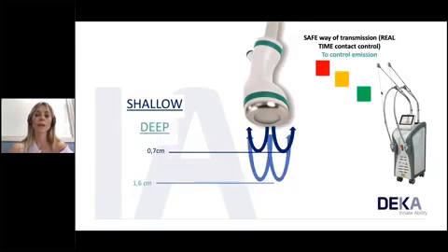And the deep end piece instead will reach 1.6 centimeter, and then it will recall back from the electrode. So the transmission is safe because no vital organs will be involved. It's safe for the patient, but it's also safe for the physician, because even if we carelessly lose contact with the skin, we are sure that the microwaves will be recalled back.